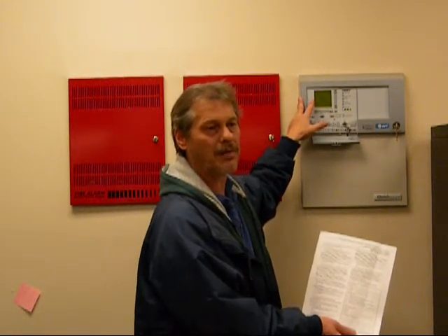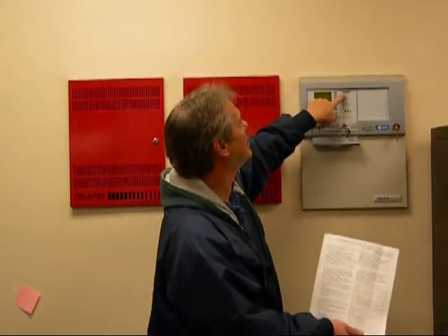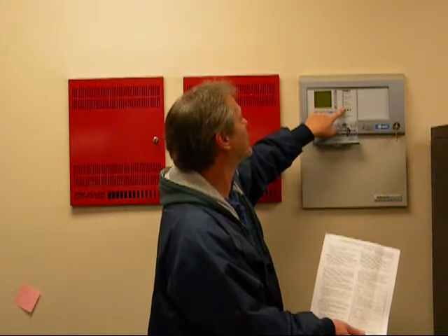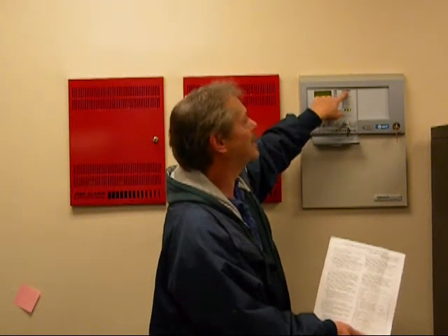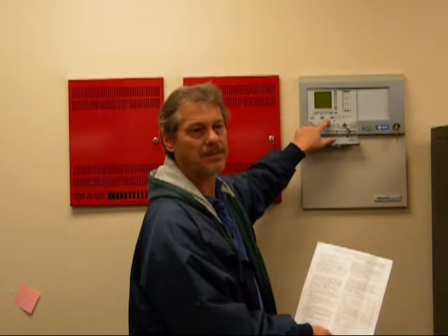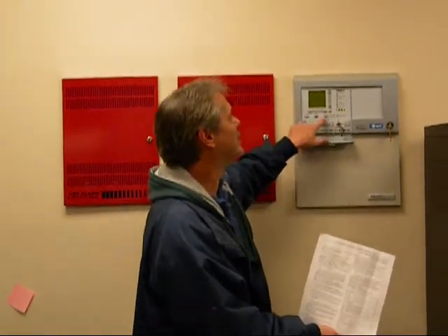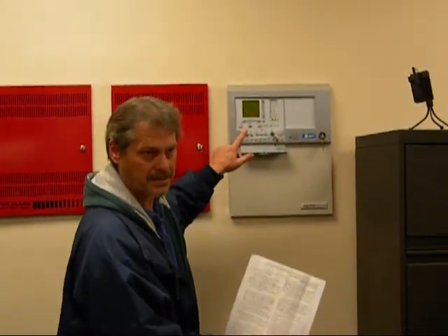And like I said, the fire alarm is going to be the highest signal. Normally, there are LEDs here that will light up for different conditions. And we're concerned with the alarm LED at the top. Okay, if a fire alarm occurs, this LED is going to flash. It's going to continue to flash until you actually acknowledge that signal. I'm not saying silence the alarm, I'm saying acknowledge the signal. Two different things. Okay, silencing the alarm and acknowledging a signal are two different buttons.